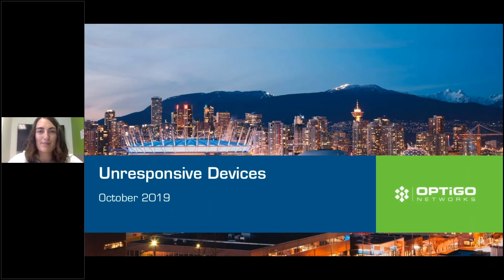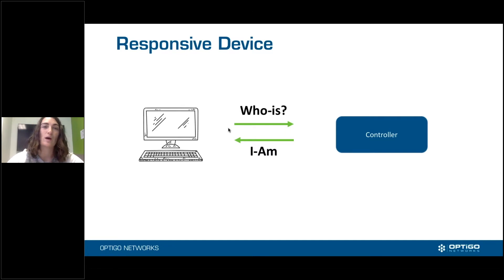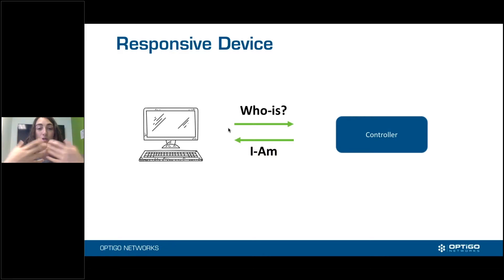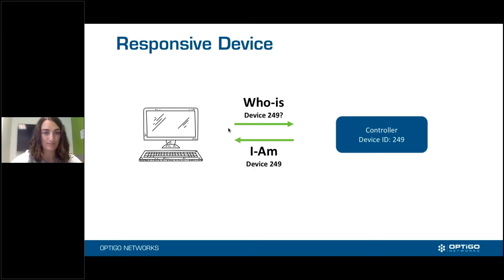Hi everyone, welcome. My name is Monica McMahon and I'm so happy to be here today talking to you about unresponsive devices. We are going to jump right into it. So what is an unresponsive device? It's a device that's not responding, as the name implies.